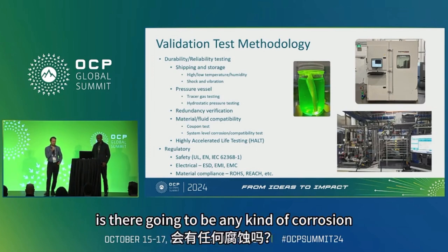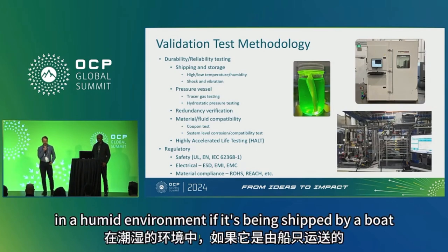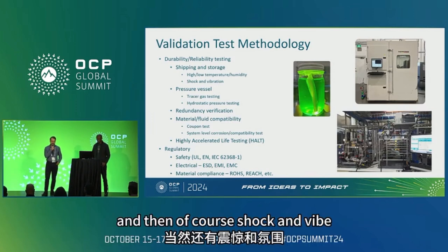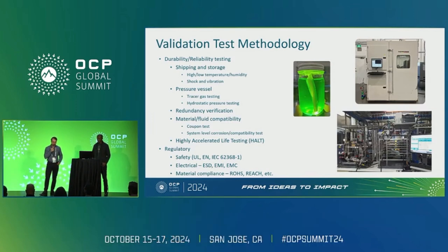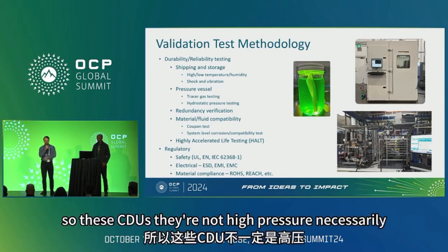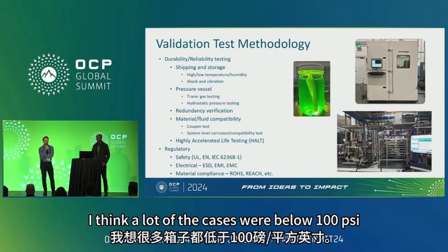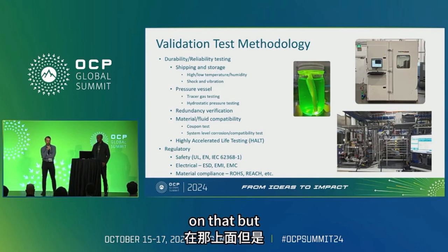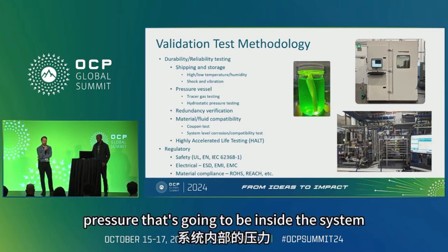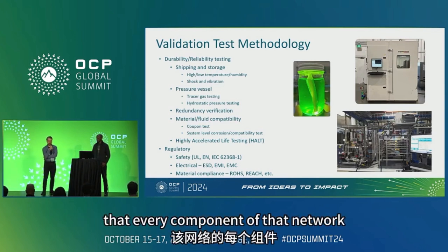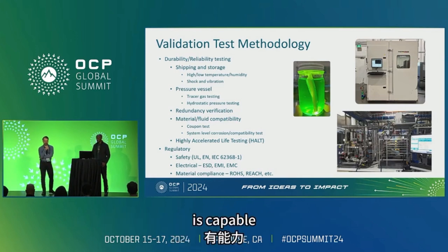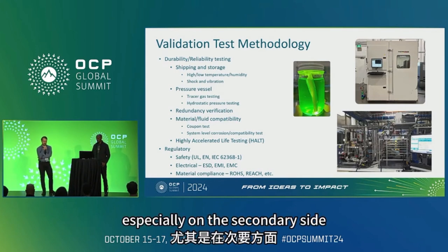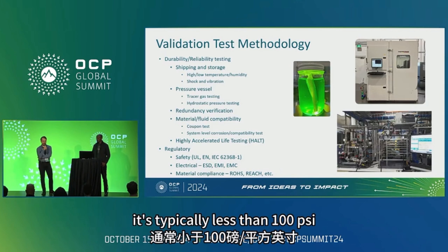Is there going to be any kind of corrosion in a humid environment if it's being shipped by a boat? Those types of things. And then, of course, shock and vibe. Pressure vessel as well. So these CDUs, they're not high pressure necessarily. I think a lot of the cases were below 100 psi on that. But making sure that it can withstand the pressure that's going to be inside the system, that every component of that network is capable. Especially on the secondary side, it's typically less than 100 psi.